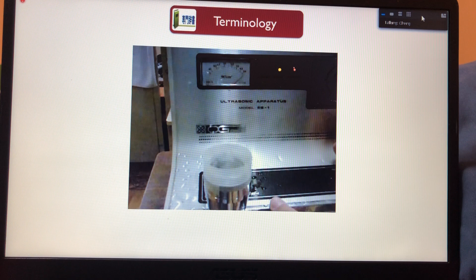Why are these important? Because of the BNR, the beam non-uniformity ratio, which is actually SPI over SAI, is to 1. So just before I finish that, we want BNR to be as low as possible, so that you get a smooth feel. Now, 20 years ago, it was not as good. It was like 10 is to 1. Before that, it was even like 20 is to 1. So the peak intensity right at the center there can cause hotspots. So people would pulse it so that you don't get as many hotspots. But with the present devices, the good transducers, the BNR is as low as 2:1. So you don't have that problem of hotspots, which means that you may not need to pulse. We'll come back to pulse in a short while.